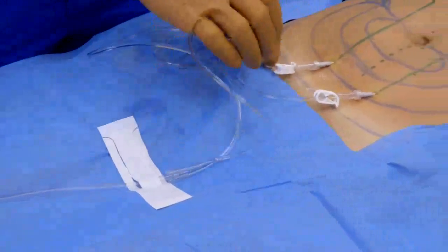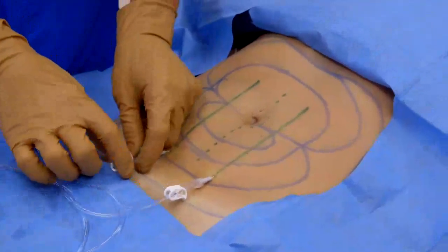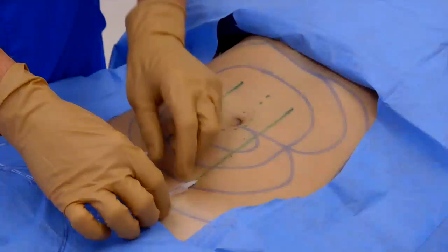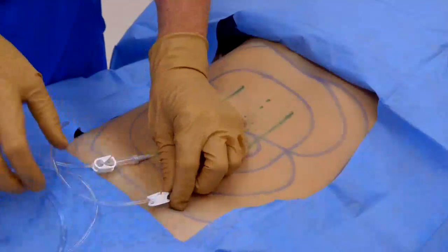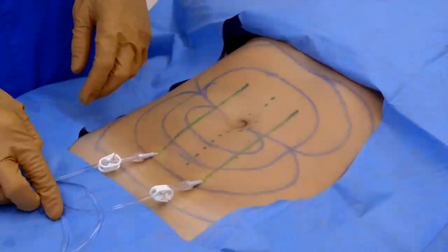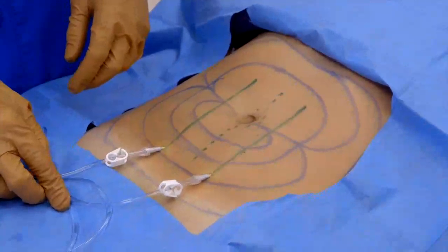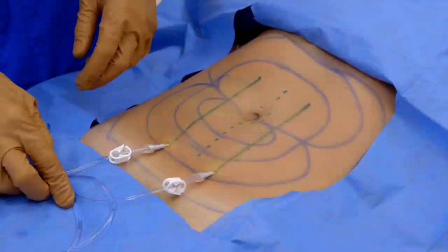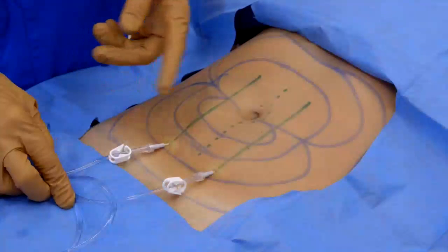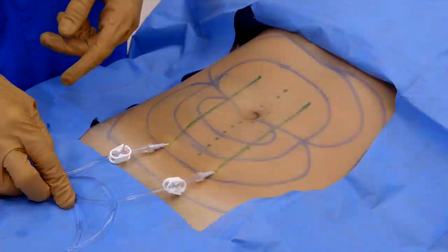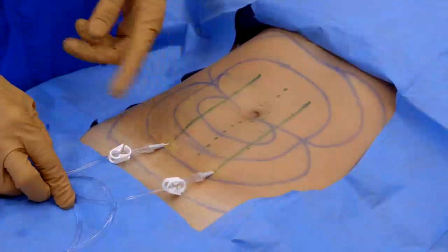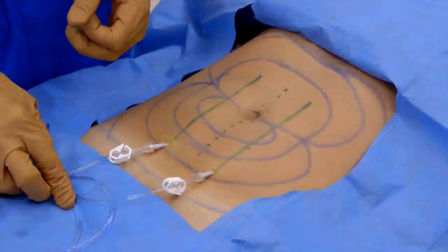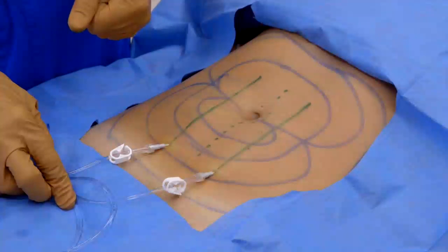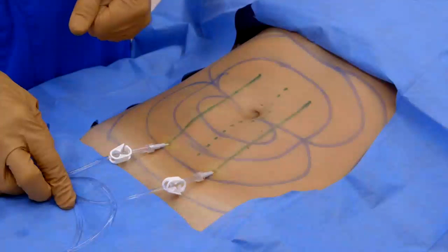We're now ready to begin tumescent infiltration. First, open the clamps. By stepping on the actuator for the tumescent infiltration pump, the peristaltic pump, the fluid will begin flowing. Typically, we'll have the pump set at approximately 200 milliliters per minute infiltration rate.